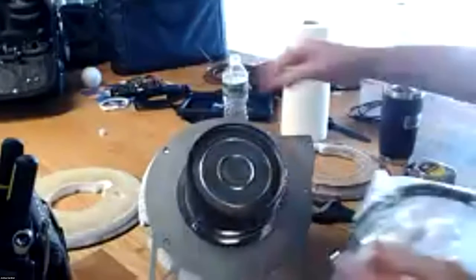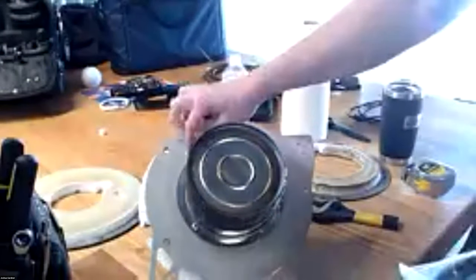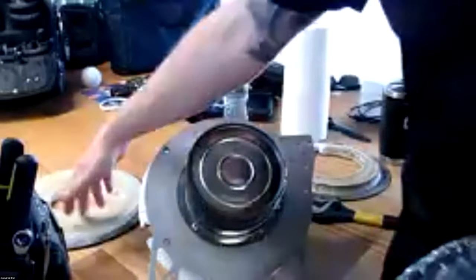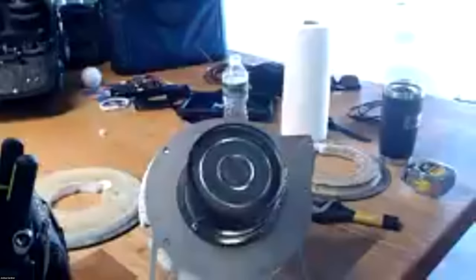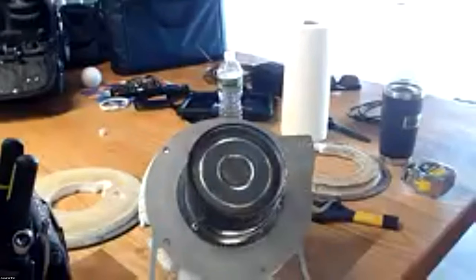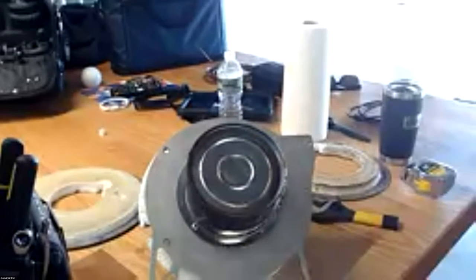No, the gasket that's in between the burner head here comes with it. That gasket, this insulation doesn't. It's separate. Got it. Would you change that one when you do pull it off, or is it good to reuse? I'd probably change. Well, depending, and there's a lot depending on it, the burner setup, propane, whatever. But chances are you're not going to have to change that every year. Maybe you change it every 3 to 4 years. But that's if you're not venting properly, you start overheating in the top here, you get discoloration.